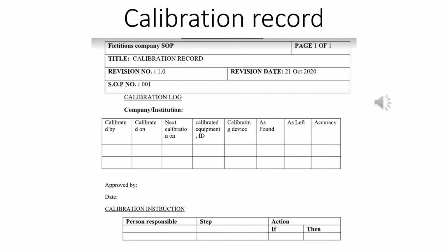So the calibration log should be written down, and it is also called the calibration record or calibration log. Just write down the company name or institution name, who calibrated it, when it was calibrated, and when the next calibration is. It could be next month, after a year, after 3 months, after 6 months, and what equipment is being calibrated.